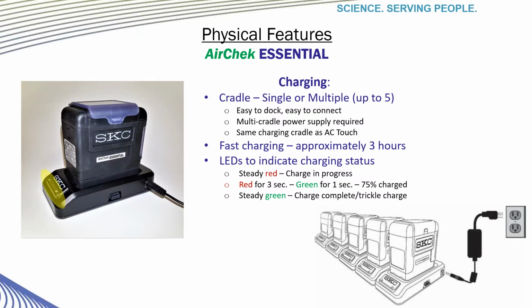The charging cradle has status LEDs to indicate the status of the charge. A steady red light just means that the charge is in process. A red indicator for 3 seconds, followed by a green indicator for 1 second, means that your battery is about 75% charged. When you get a steady green light, your battery is fully charged and the charger will go into trickle mode to keep the battery from overheating, but also it will keep the battery at full charge so it's ready when you need it.